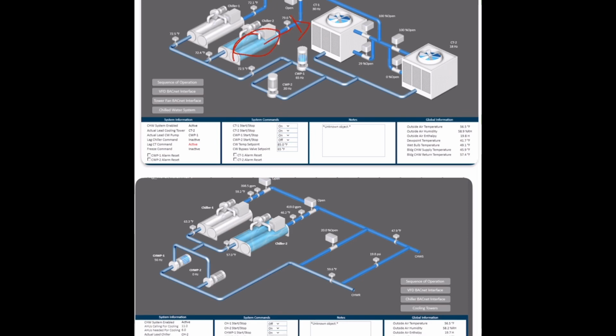This is our condenser, which has the water. Water is gonna flow through this line, and it's gonna go all the way to a line. Then it's gonna go on top of our cooling towers, both of them. Then the water is gonna run down through the fill of the cooling tower. That fan is gonna be running, and it's gonna be lowering the temperature or cooling down our water. That is gonna go back through this pump, and it's gonna go all the way back to our condenser on the chiller right there. So in our condenser is where the subcooling is happening. Instead of using air, we're using water.